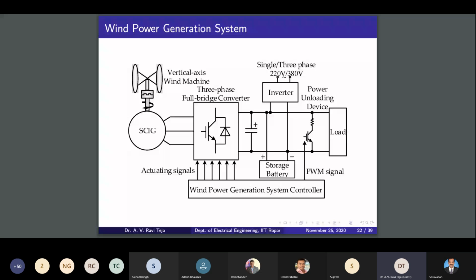If you don't want this power to drop, or if you want higher efficiency, then you have to drop the gearbox and directly feed the generator. But in that case, with the small speed, you have to have some voltage boosting circuits also, so that you get a higher voltage at the output of the generator, because the speed is very small. Or you may have to go for a specially designed generator which can work at very low speeds also, right?